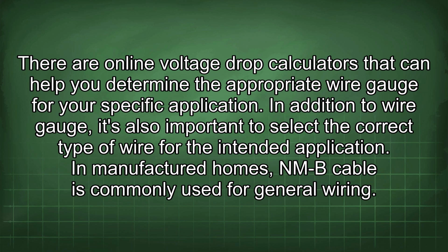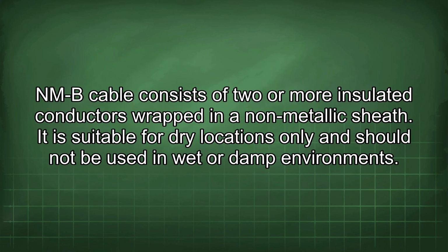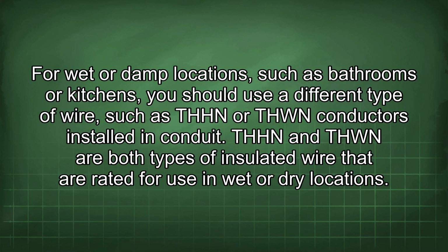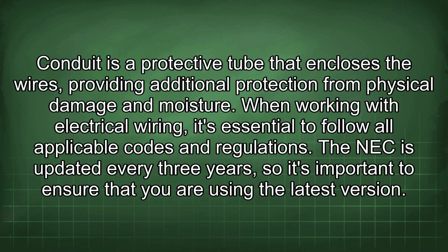In addition to wire gauge, it's also important to select the correct type of wire for the intended application. In manufactured homes, NMB cable is commonly used for general wiring. NMB cable consists of 2 or more insulated conductors wrapped in a non-metallic sheath. It is suitable for dry locations only and should not be used in wet or damp environments. For wet or damp locations, such as bathrooms or kitchens, you should use a different type of wire, such as THHN or THWN conductors installed in conduit. THHN and THWN are both types of insulated wire that are rated for use in wet or dry locations. Conduit is a protective tube that encloses the wires, providing additional protection from physical damage and moisture.